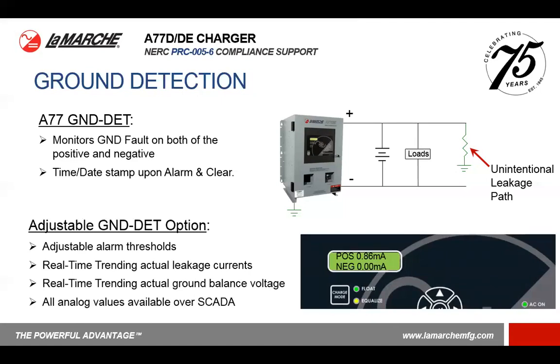We also have availability for adjustable ground detection options, and this allows us to adjust the alarm trigger thresholds for the ground detection, as well as add in capabilities for remote real-time trending of actual leakage currents and the ground balance voltage. And all of these analog values are available over SCADA. You might be using a third-party application such as Pi Historian to be able to log and monitor these particular thresholds for the purpose of continuous real-time or condition-based monitoring.